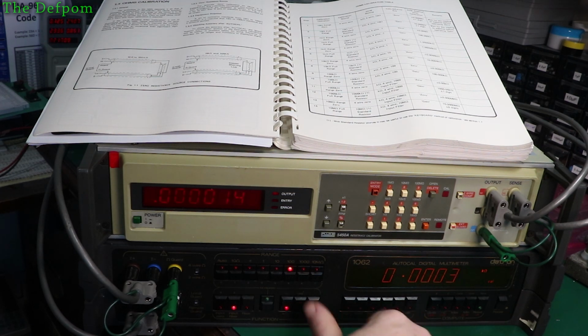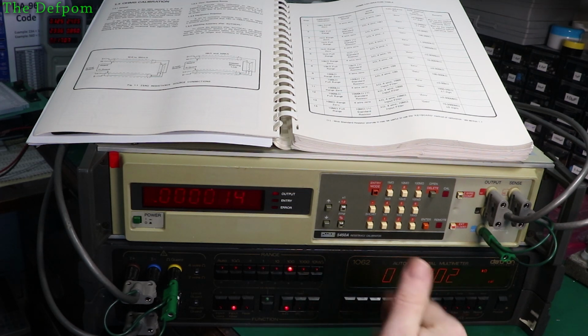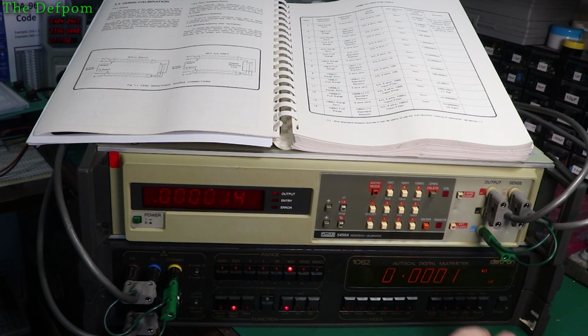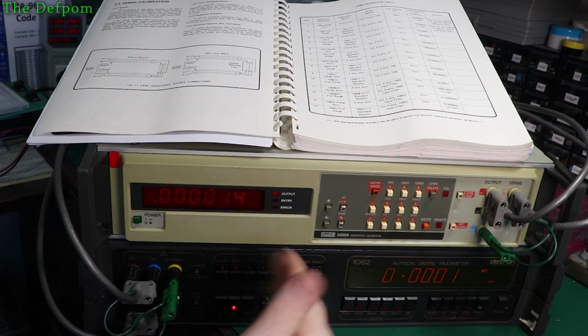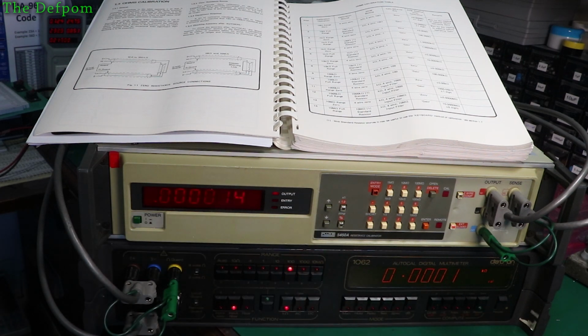And the higher the resistance, the more settling time you need to give it, because it gets more critical. Because the currents involved, each range up is 1/10 of that previous range's current. So it gets down to nanoamps in the highest ranges, so you're talking really small values, so it gets more affected by things.